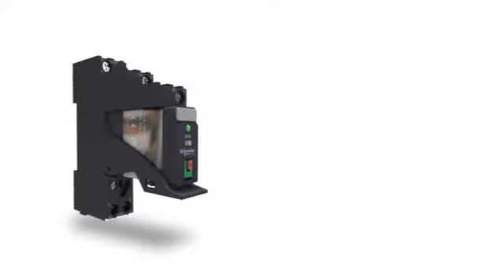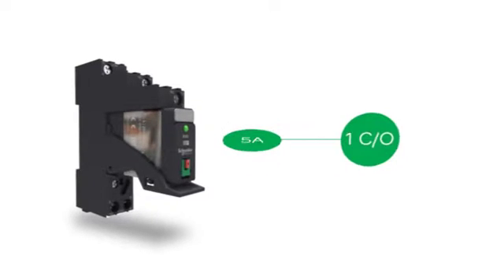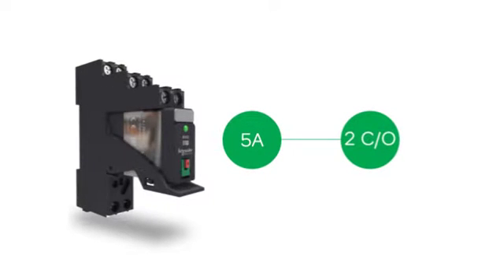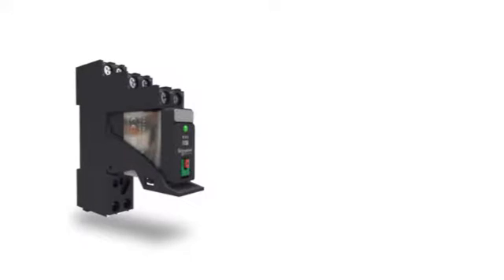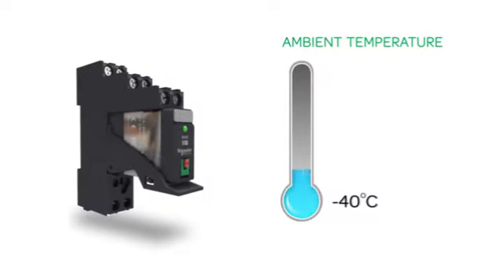The Zelio RXG interface relay range comprises sockets, 10 ampere relays with 1 changeover contact and 5 ampere relays with 2 changeover contacts. Zelio RXG can operate at an ambient temperature of negative 40 degrees Celsius to 70 degrees Celsius.